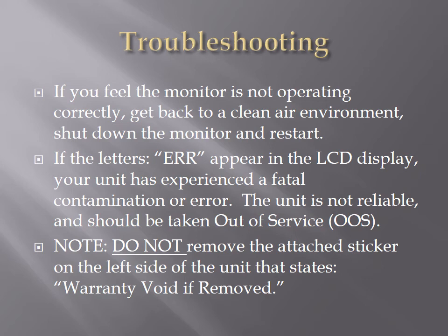It should go through its normal operational settings, its test, and hopefully go back into a monitoring mode with the green light appearing. If the letters ERR appear in the LCD display screen, I want you to understand that your unit is not going to work. It's not considered reliable, and it should be taken out of service. Again, if you have the letters ERR in the display screen, the unit is not reliable and therefore should not be used.